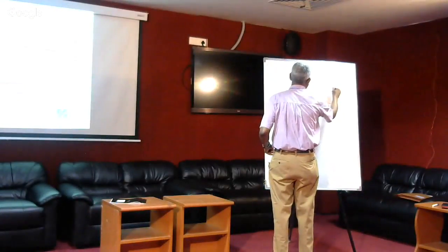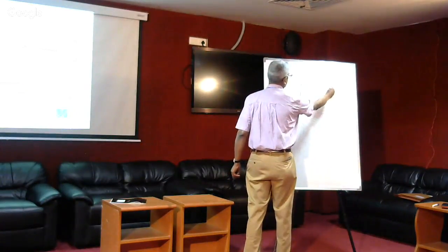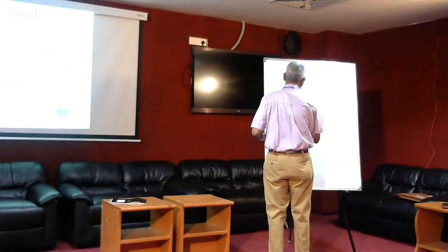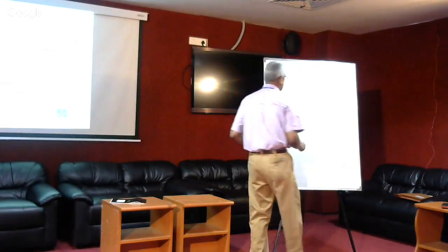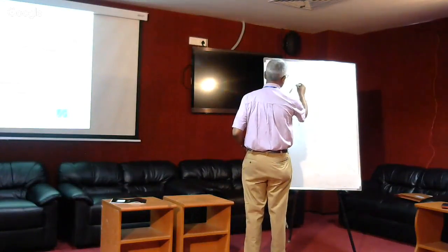In other words, what I'm trying to say is, if you have a situation like this, this is the best situation because you get non-detect and then it breaks through and it reaches the influent concentration. This you never really see in real life. What you see sometimes is what we call the S curve. So let's say this is, I'm just making up a number, 5 milligrams per liter, and your breakthrough is 0.5 milligrams.